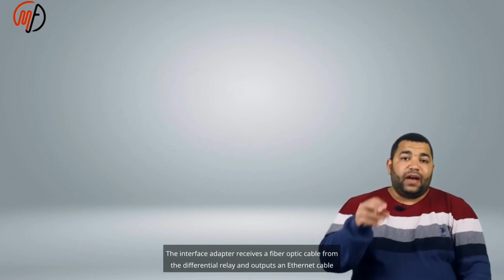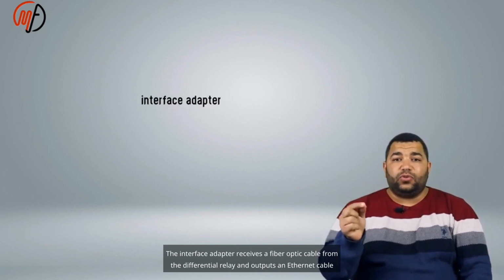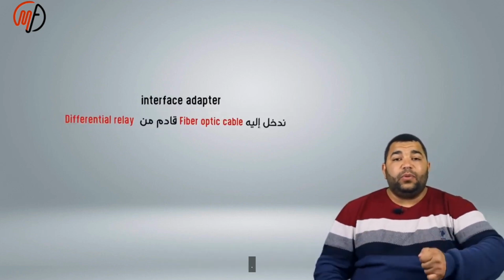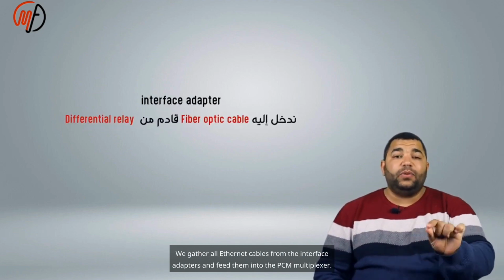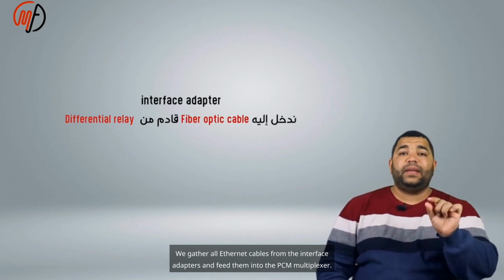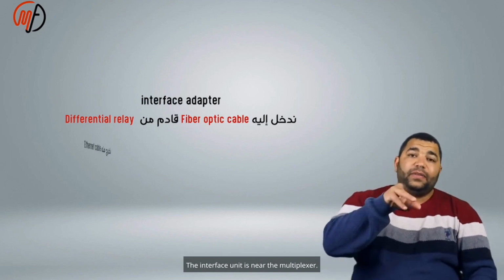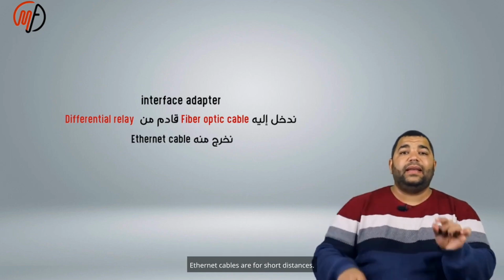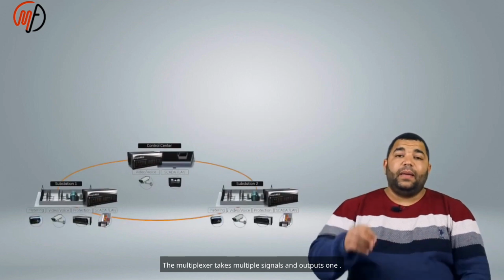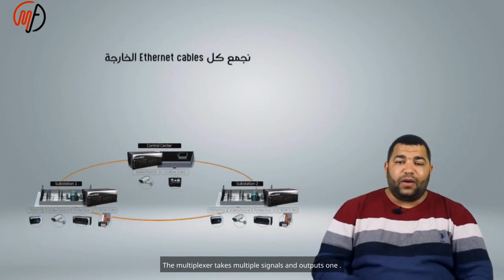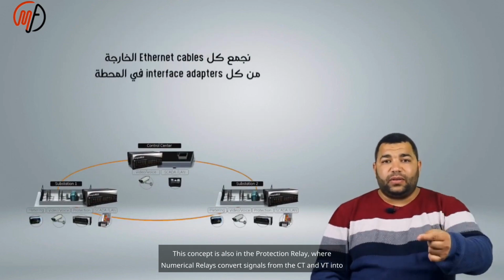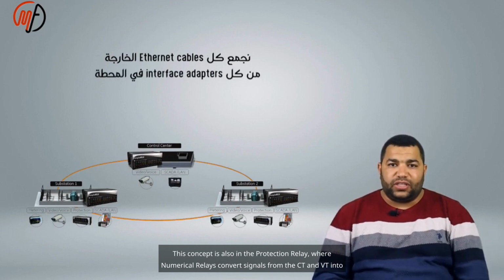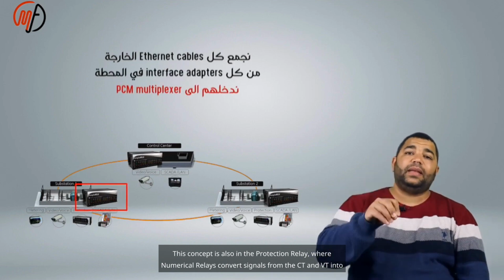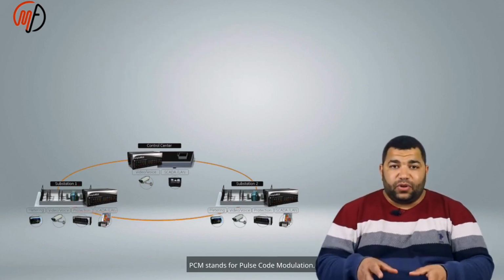Let's return to the topic. The interface adapter receives a fiber optic cable from the differential relay and outputs an Ethernet cable. We gather all Ethernet cables from the interface adapters and feed them into the PCM multiplexer. The interface unit is near the multiplexer. Ethernet cables are for short distances. The multiplexer takes multiple signals and outputs one. This concept is also in the protection relay, where numerical relays convert signals from the CT and VT into digital numbers. PCM stands for pulse code modulation.